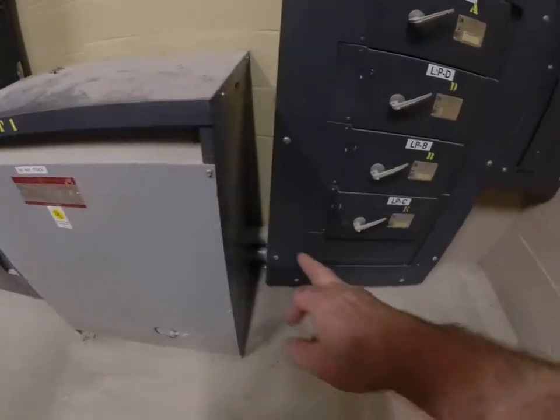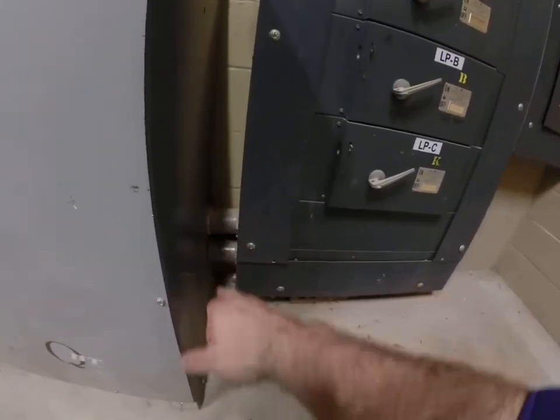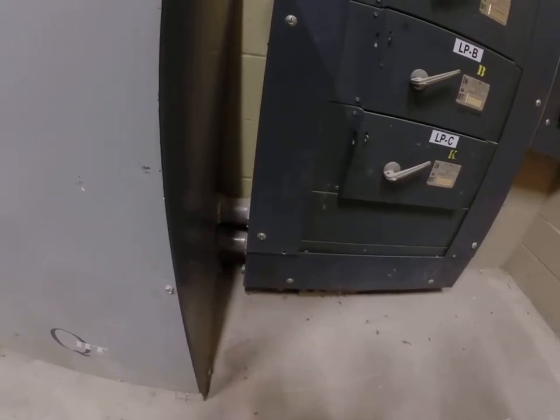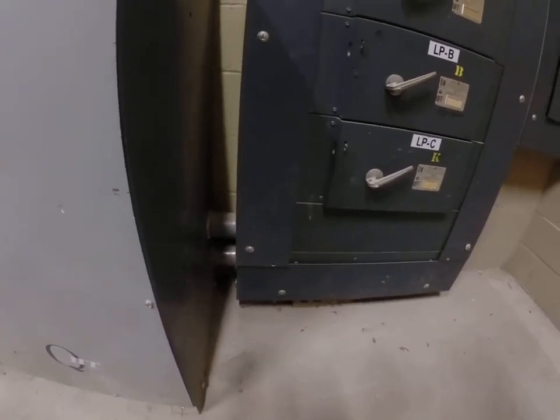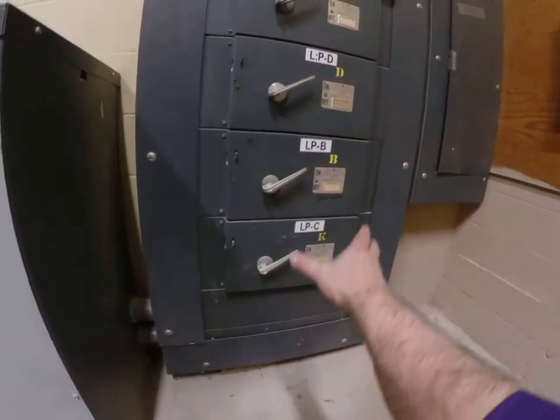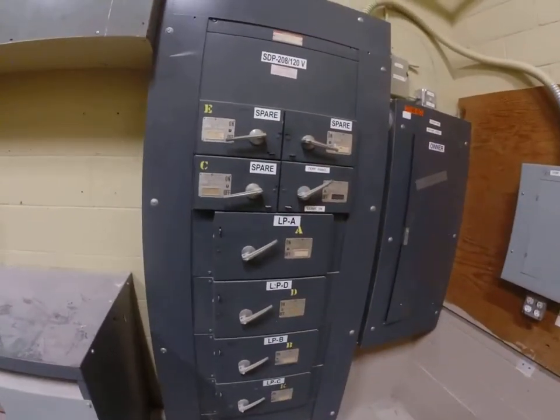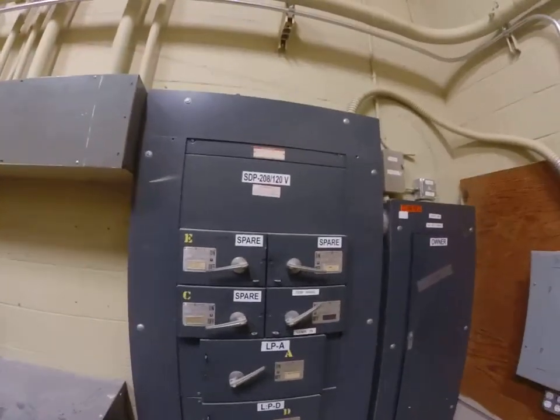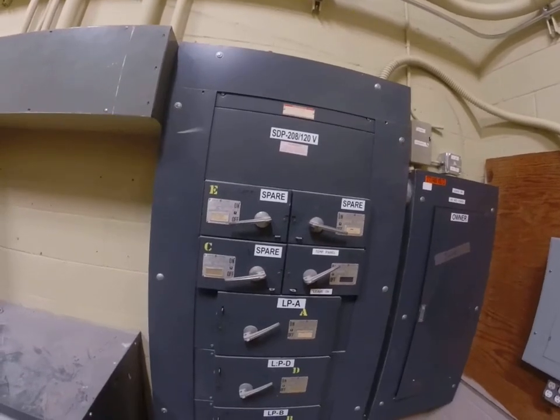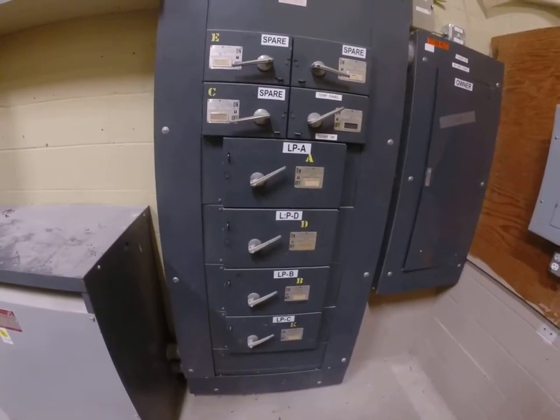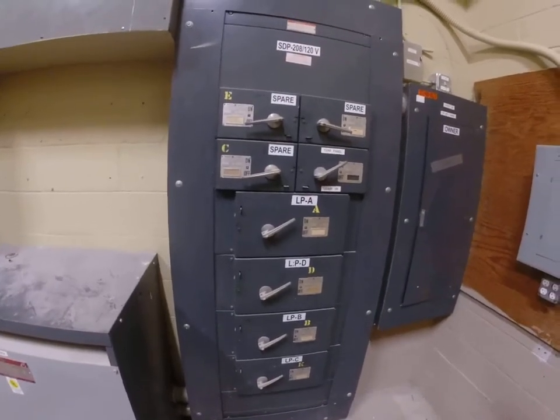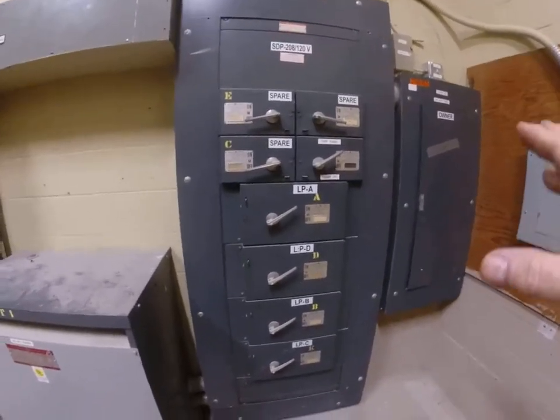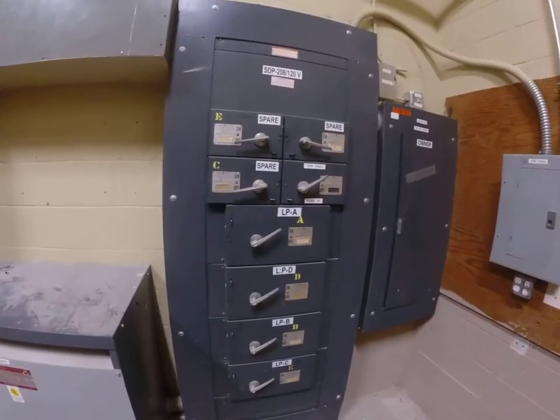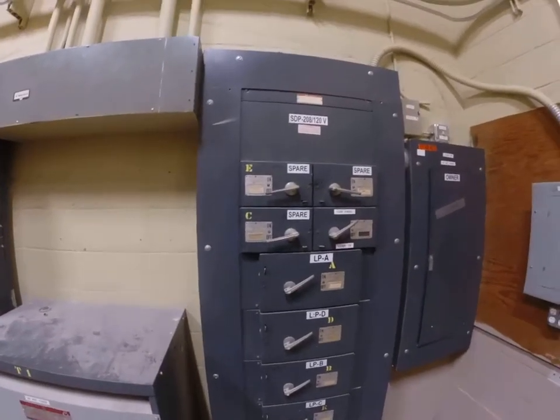And then we've got parallel feeders coming out of the side of the transformer. That's why the 2 conduits are there. That breaks this down to a usable voltage for this gear, which is 3-phase 208/120. And then if we really took this a step further, which we're going to on my next video, we'll see how Porter & Chester tapped into this feed into their electrical room, into our space that we're in now.